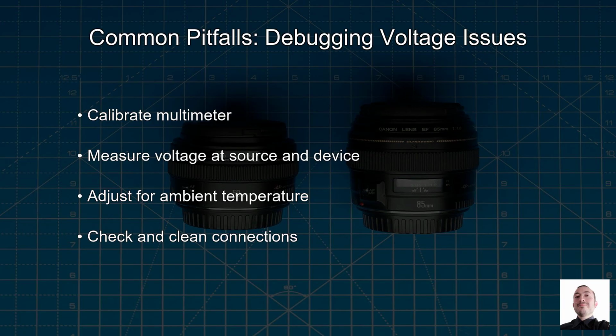Let's dive into common pitfalls when debugging voltage issues. First, ensure your multimeter is calibrated. A miscalibrated multimeter can give you false readings, leading you down the wrong troubleshooting path. Next, pay attention to voltage drop. Long cable runs can cause significant voltage drops, especially with high current applications. Measure the voltage at the source and at the device to identify any discrepancies.